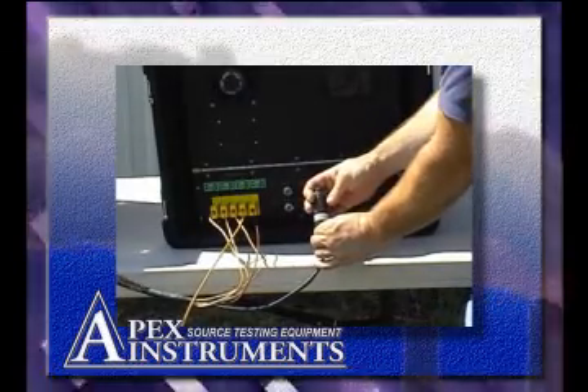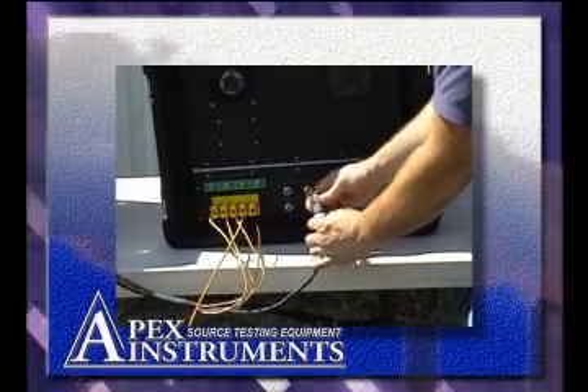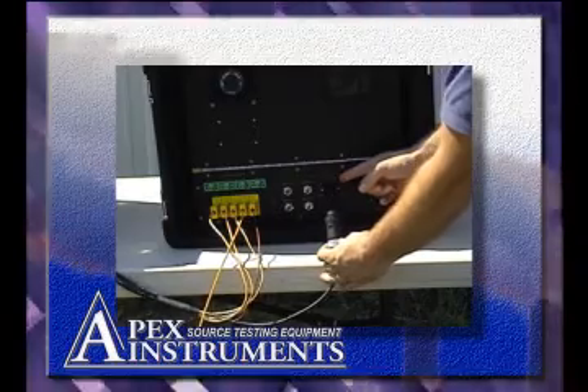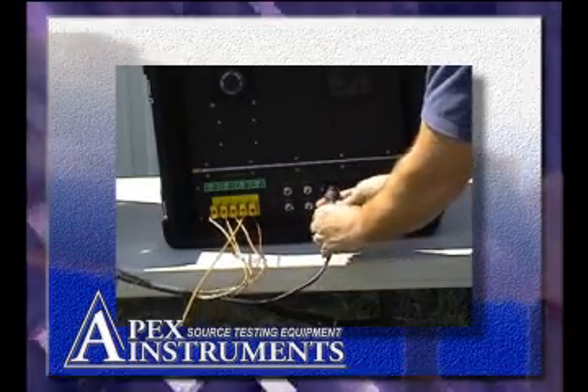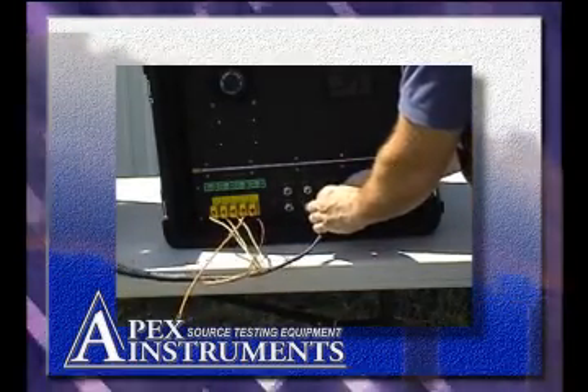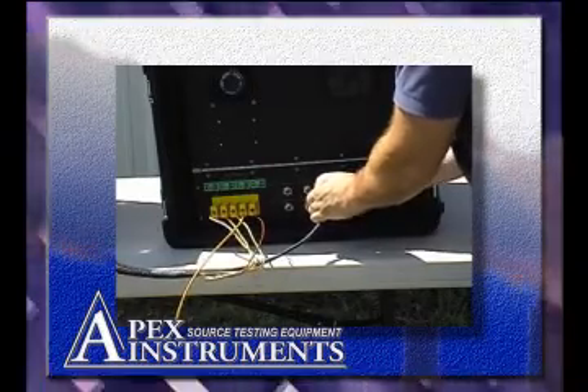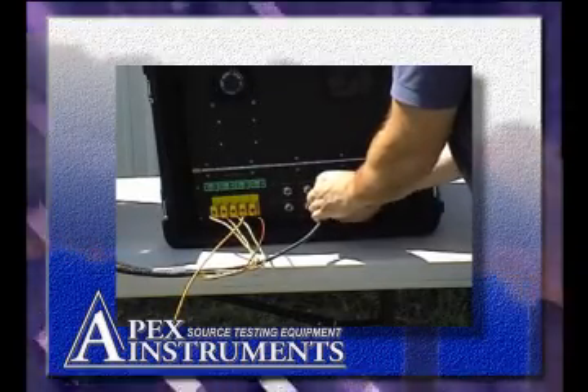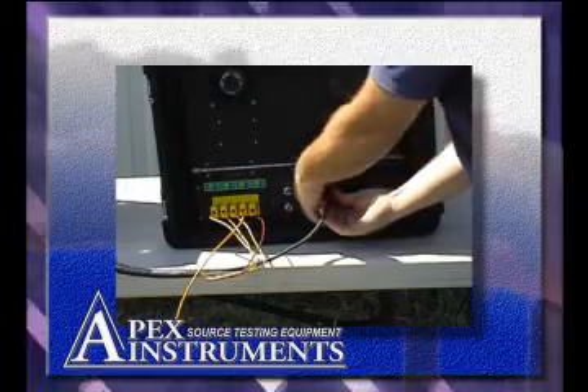The probe power connection should be made next by plugging the male probe power connector coming from the umbilical into the keyed female connector next to the main AC power connection. This connection should be tightened as tight as possible using only the fingers.